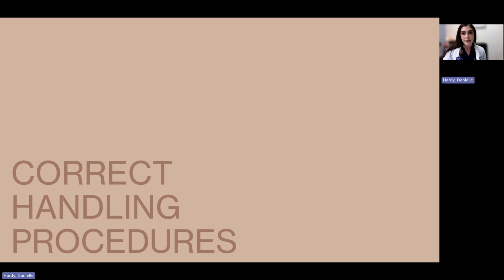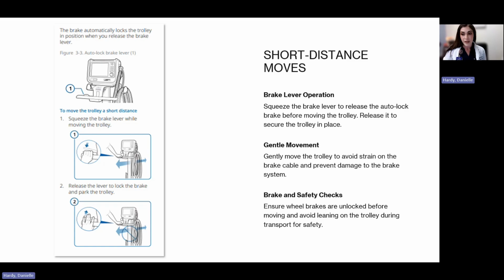We're going to review short distance moves along with long distance transport. When I say short distance moves, I mean very short, minimal distance. So when moving the trolley a short distance, such as repositioning the patient in the MRI room, the correct procedure is straightforward. First, squeeze the brake lever integrated into the handle and release the auto lock brake. Then hold the lever, gently move the trolley to the desired location, and once the trolley is in position, release the brake lever to engage the auto lock brake and secure the trolley.